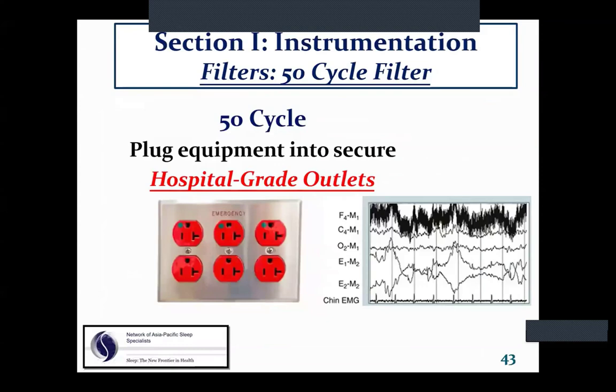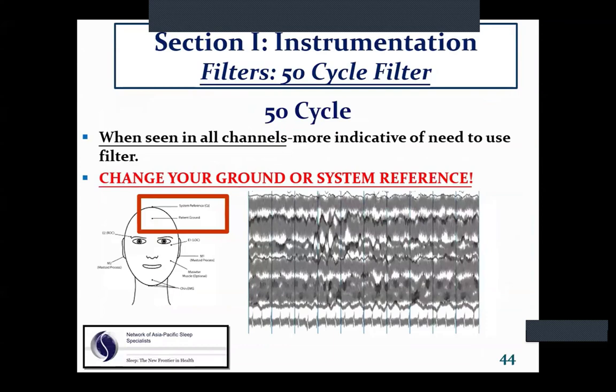It's important to plug your equipment into hospital grade outlets. Now, in this example, the outlets are red, but more and more I'm seeing them green. So make sure you're plugged into a hospital grade outlet. So the rules for using the 50 hertz or 50 cycle filter is when you see it in all channels and after you change your ground or system reference. Now, not all systems in sleep have a system reference. So you may or may not have that, but definitely change your ground.